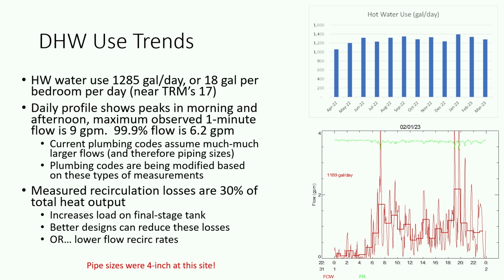Water use: in the previous session, I don't know if you were in there, we talked about what water use is per person and per apartment. We found that in this building we use 1,285 gallons a day, and the average per bedroom, if you assume a bedroom is the same as a person, was about 18 gallons a day, so we saw usage right where we expected. And here's the profile that we saw across the day. Here's the hourly profile, the square. And if I look at the instantaneous 1 minute use, we do see high fluctuations.